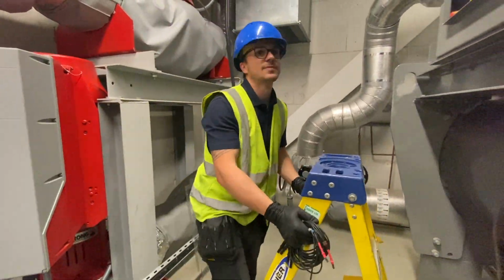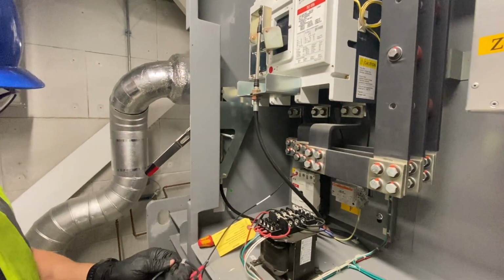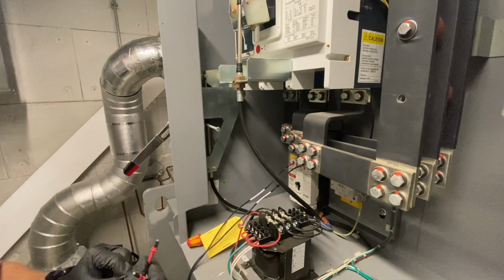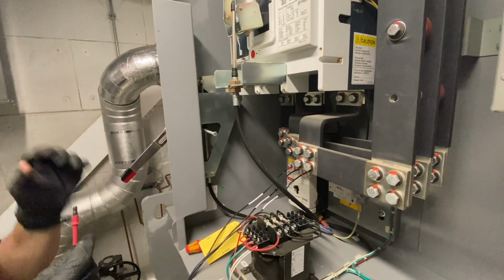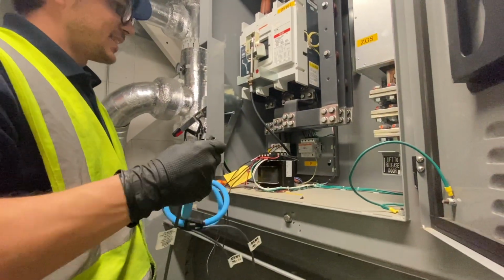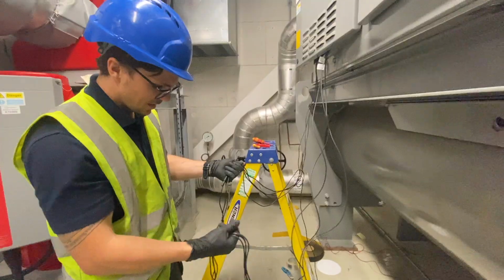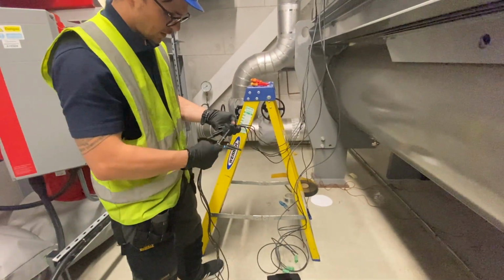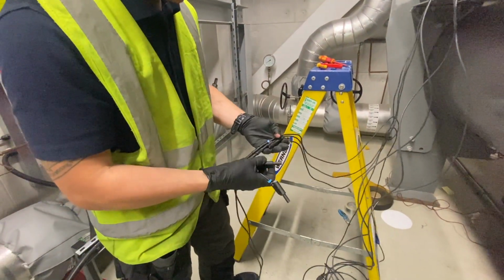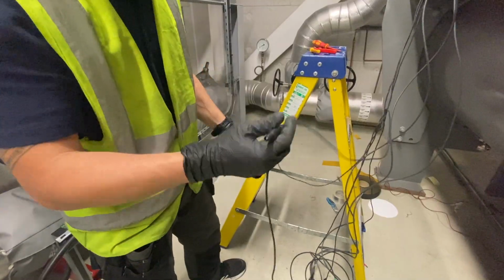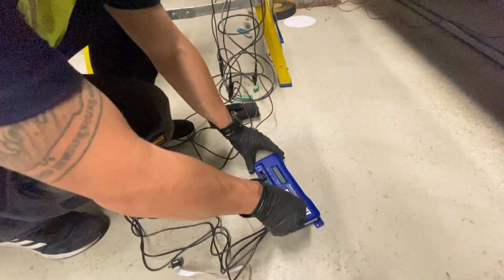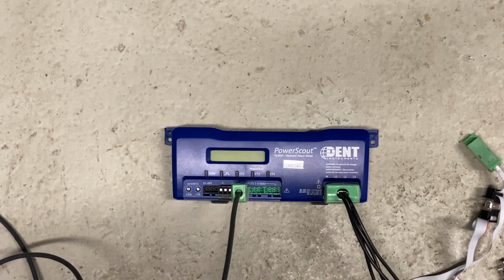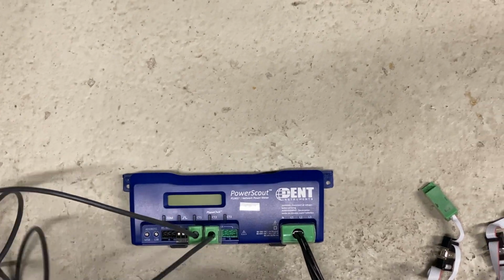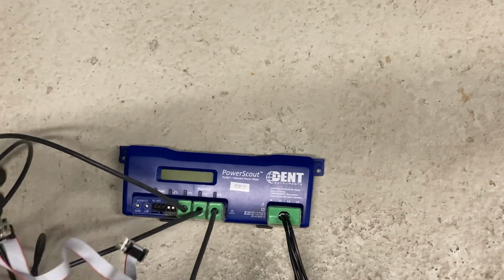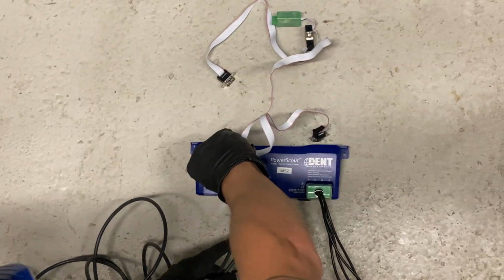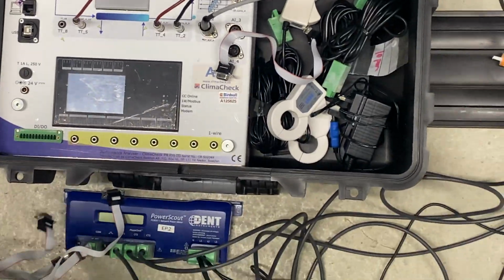With the next few slides we'll see the engineer connecting into the electrical side of the chiller, first isolating up with the panel. Now he's fitting the magnetic voltage sensors. Next he's got the power clamp that will measure the amperage of each phase off the bus bars. Now we're fitting extension cables and transfer cables which will allow the sensors to be plugged into the jack points of the Power Scout. And there's the Power Scout with the amperage and the voltage connections being made. And now we're putting on a connection data cable which will transfer all that data directly into the relevant part of the portable ClimaCheck.